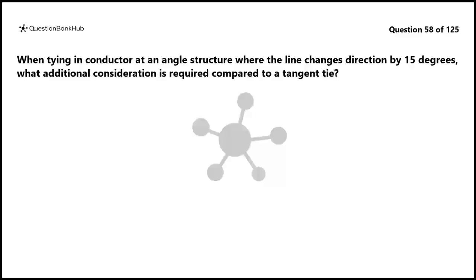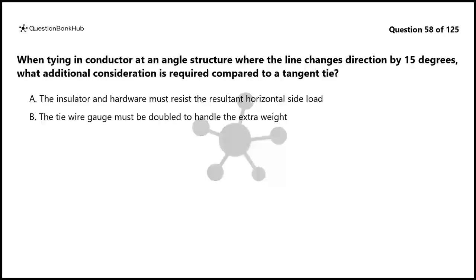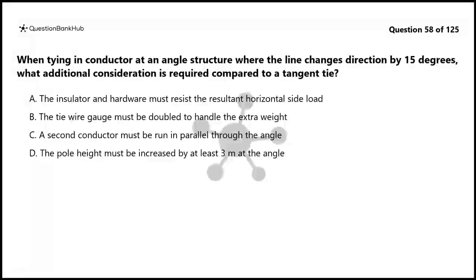Question 58. When tying in conductor at an angle structure where the line changes direction by 15 degrees, what additional consideration is required compared to a tangent tie? A. The insulator and hardware must resist the resultant horizontal side load. B. The tie wire gauge must be doubled to handle the extra weight. C. A second conductor must be run in parallel through the angle. D. The pole height must be increased by at least 3 meters at the angle.